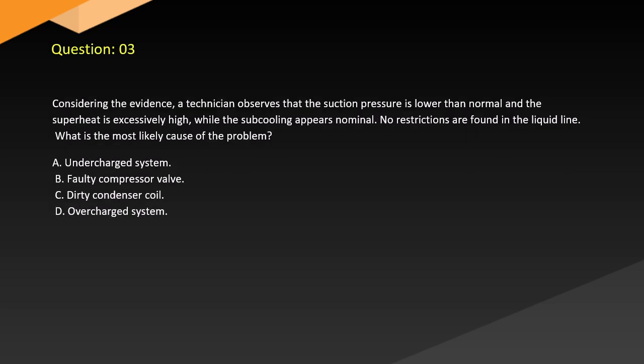Question 3. Considering the evidence, a technician observes that the suction pressure is lower than normal and the superheat is excessively high, while the subcooling appears nominal. No restrictions are found in the liquid line. What is the most likely cause of the problem? A. Undercharged system. B. Faulty compressor valve. C. Dirty condenser coil. D. Overcharged system.